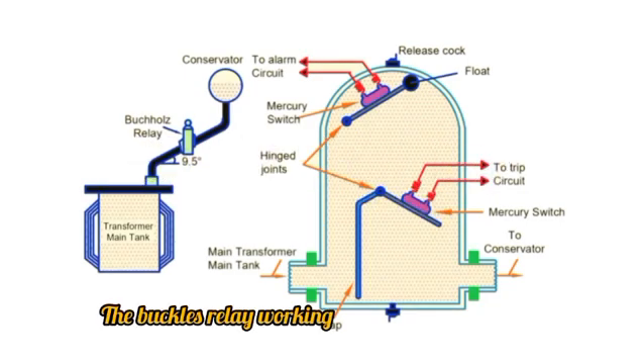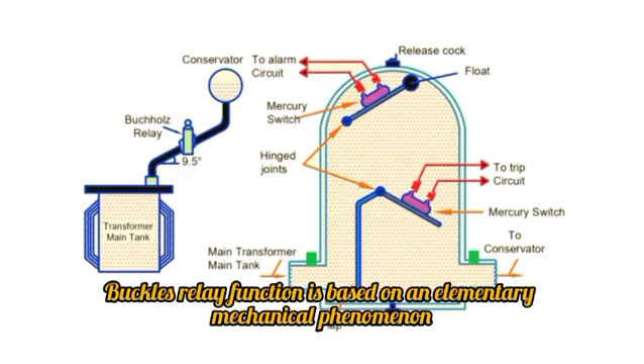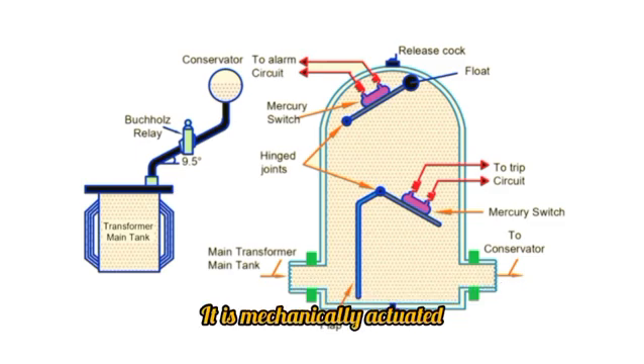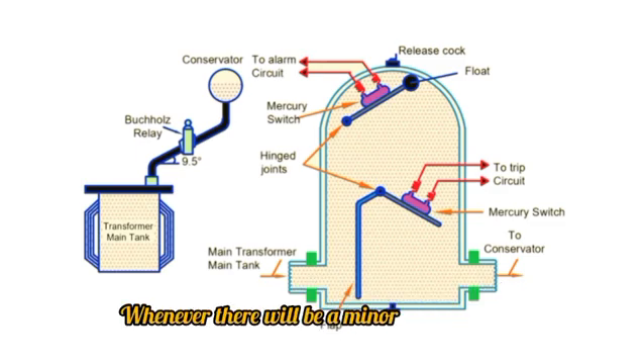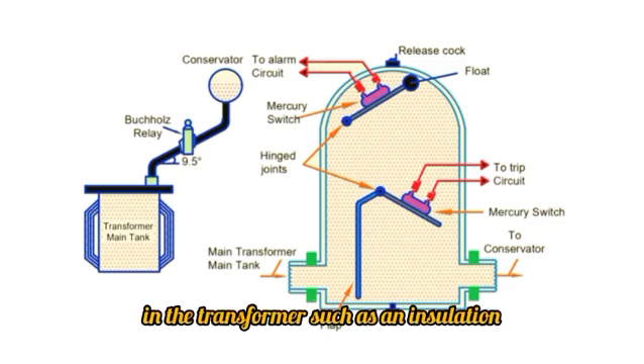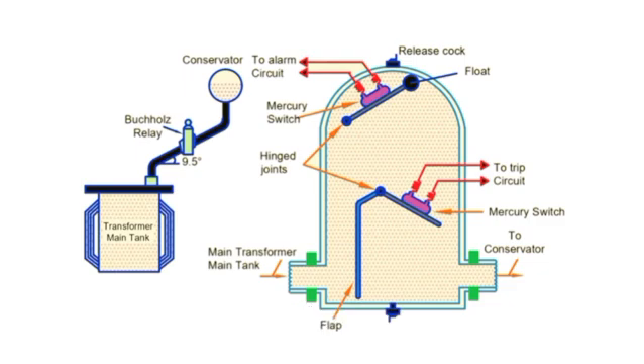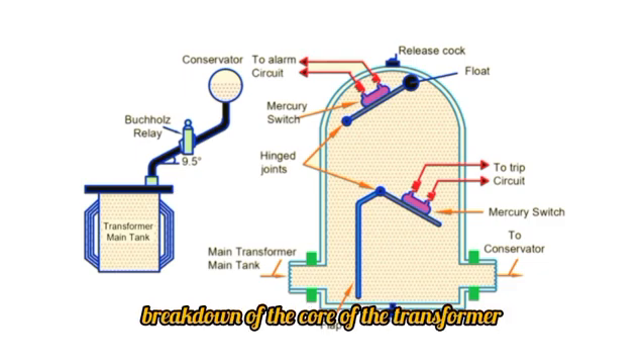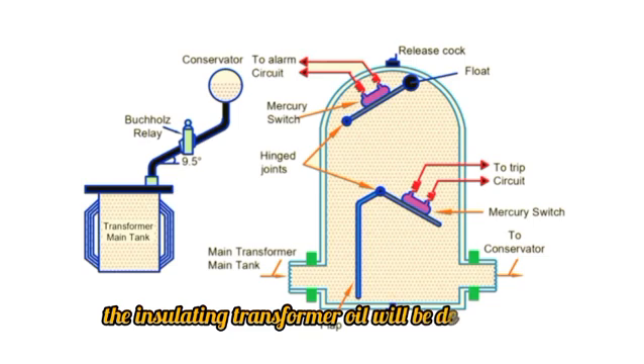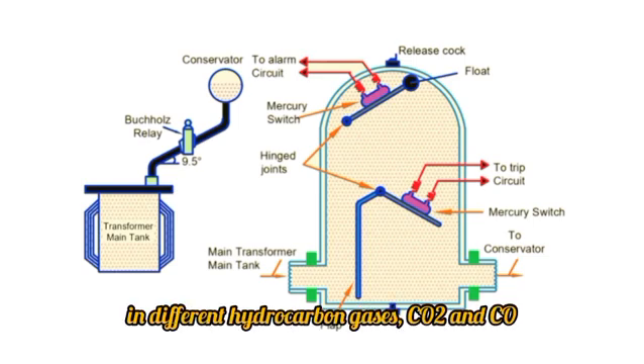Working principle of Buchholz relay. The Buchholz relay working principle is very simple. Buchholz relay function is based on an elementary mechanical phenomenon. It is mechanically actuated. Whenever there is a minor internal fault in the transformer, such as an insulation fault between turns, breakdown of the core of the transformer, and core heating, the insulating transformer oil will be decomposed into different hydrocarbon gases, CO2 and CO.